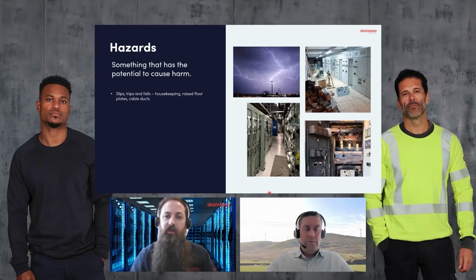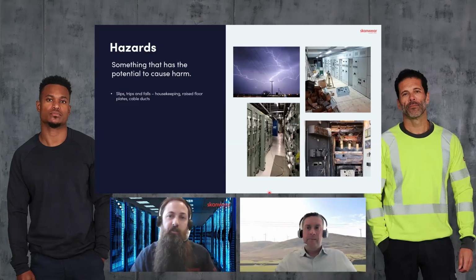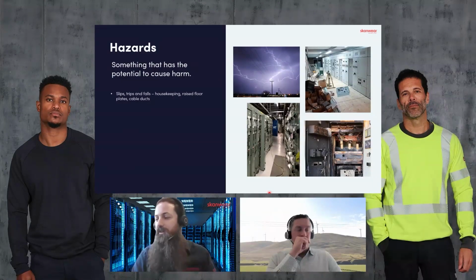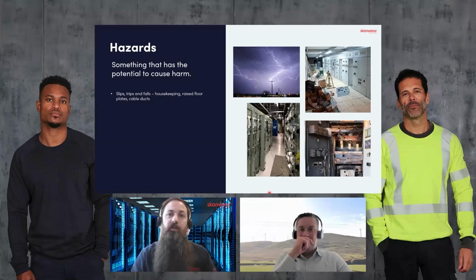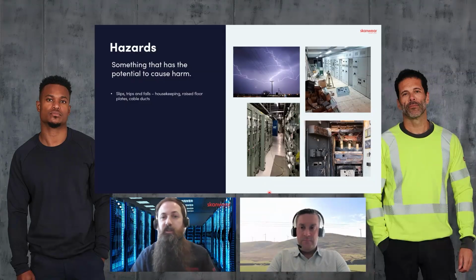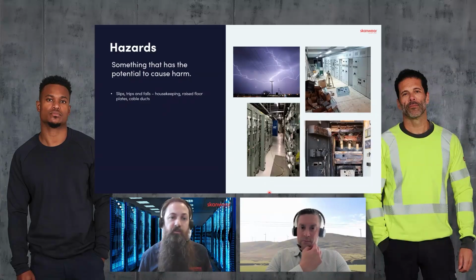So if it is an outage, you might introduce a housekeeping issue where you've got trailing leads for test equipment, even vacuum cleaners, things like that when you're doing maintenance. Often you're not going to tidy before you restore supplies - your time's at a premium during an outage, so when you're trying to get the power back on, housekeeping becomes an afterthought. Even the most diligent engineers, under time pressure, often leave the housekeeping side. Raised floor plates when checking for water ingress in cable ducts, or doing repairs - these all introduce slips, trips and falls potential in these spaces, and it's something that's always prevalent within substations.